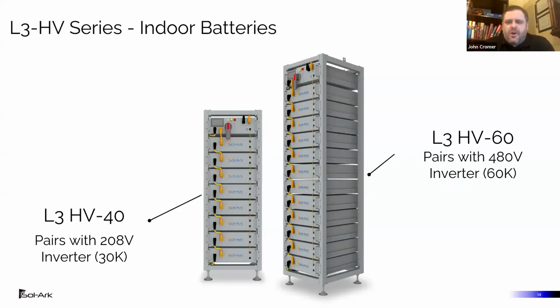Perhaps the tricky part of the design is that we have a slightly different battery cabinet for the indoor version, depending on whether you're using our 208 volt 30K inverter or our 480 volt 60K inverter. And that's because the battery bus operates at a slightly different voltage. So when you're ordering your design, you basically say, am I on 208 volt service? Am I indoor or outdoor? And then am I on 480 volt service? Am I indoor or outdoor? And so for 208 volt indoor, we're on a 40 kilowatt hour stack. And with a 480 volt indoor, we're on a 60 kilowatt hour stack.